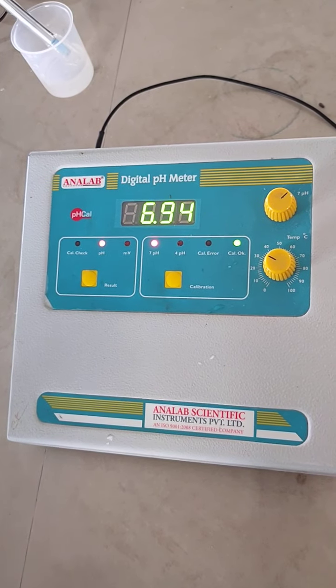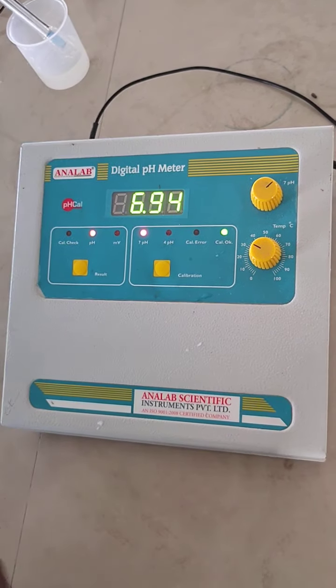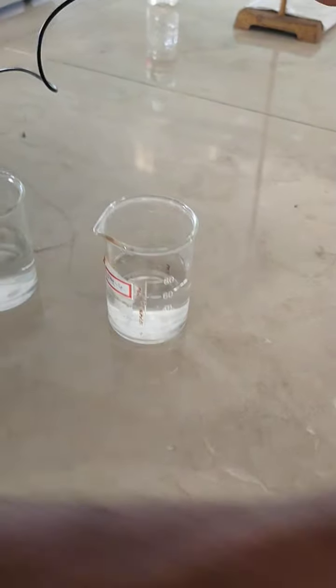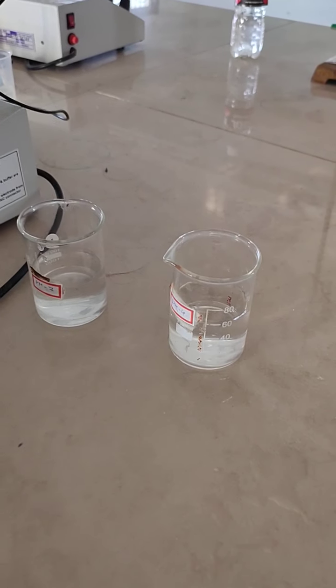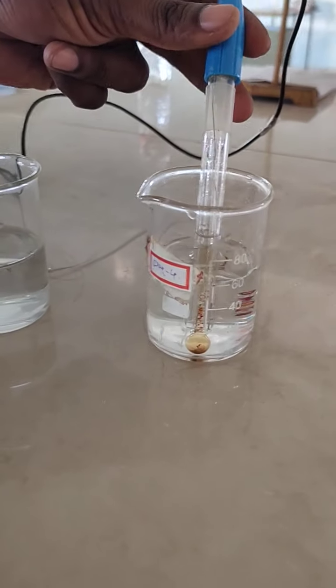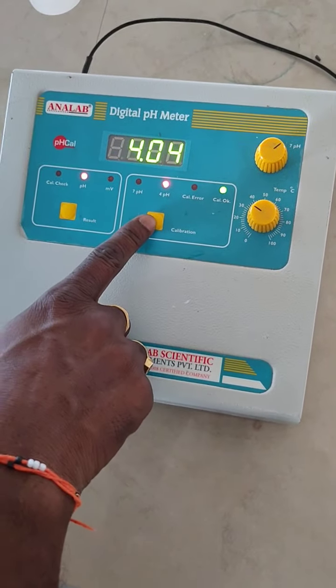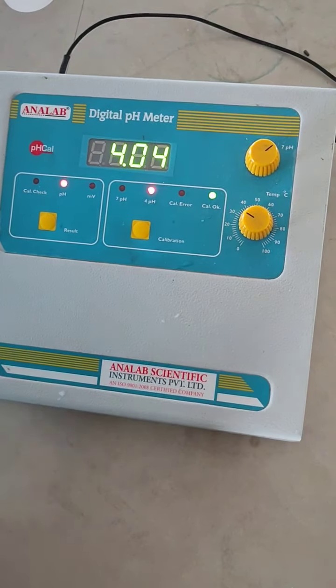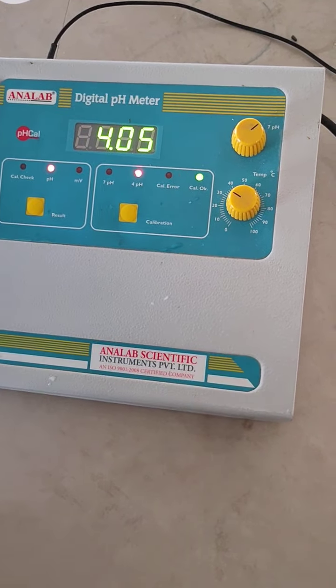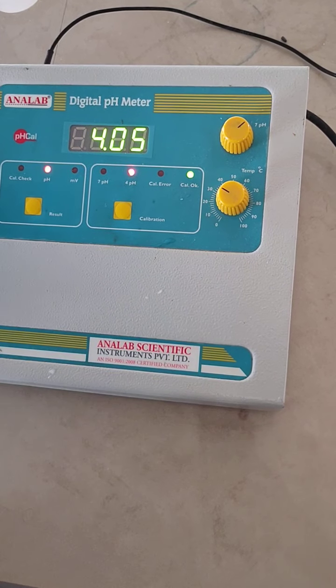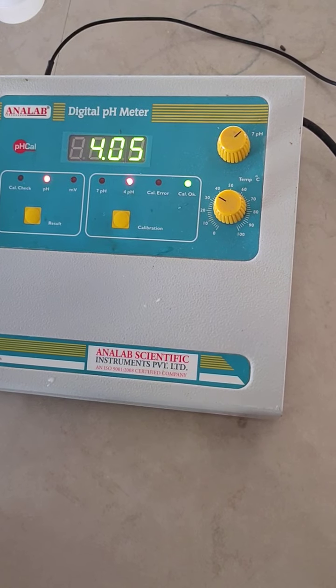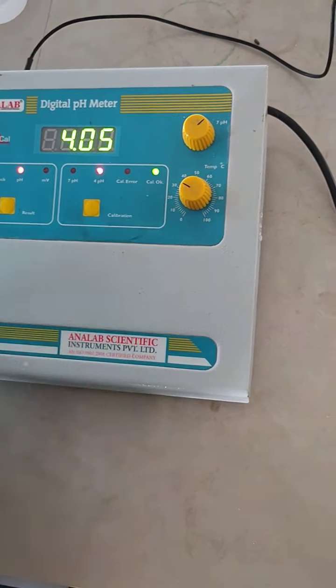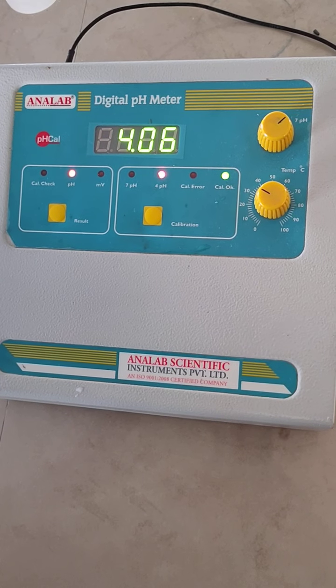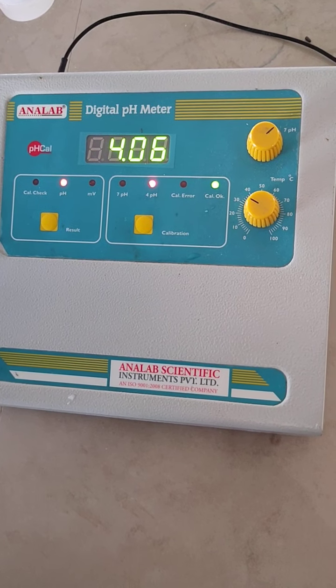Okay. See once again, I am dipping the electrode in pH 4. So then wash the electrode. And put this electrode in pH 4 solution and see the reading. So I am selecting pH 4. Then it shows 4.0 value. That means the calibration part is okay. Calibration part is good. Okay, if you do this process of 7 and 4 several times, the meter checks the calibration part. And then only the meter shows the exact results if you dip the electrode in analyte solution.